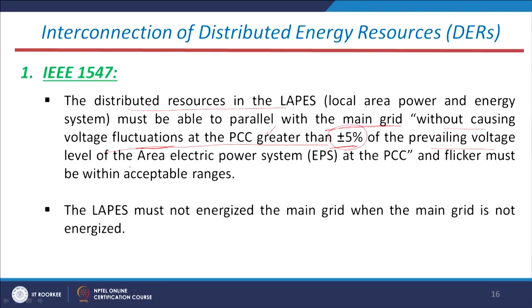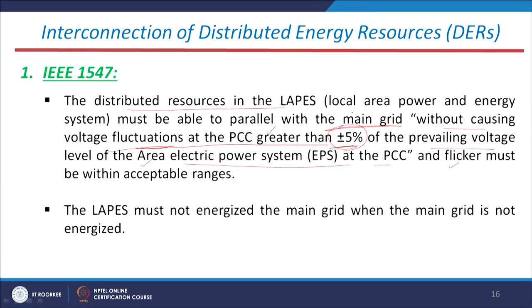The prevailing voltage level at the PCC and the flicker must be within acceptable limits. Flicker is a power quality issue — along with voltage sag, swell, and voltage interruption. The DERs must be connected in such a manner that they do not create flickering at the PCC bus, and voltage fluctuations must not exceed plus or minus 5 percent of the nominal value at the PCC bus, which is the connection point where DERs are interconnected with the main grid.